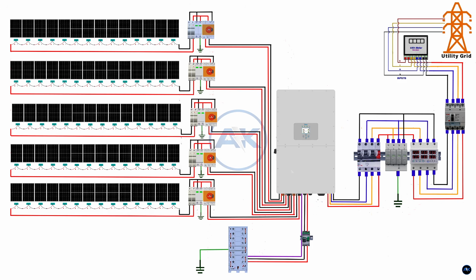Now we connect the inverter to the grid. At the inverter grid input, connect L1, L2, L3, neutral, and ground exactly as labeled. Tighten all terminals properly and confirm correct phase order. Incorrect phase sequence can cause inverter faults.